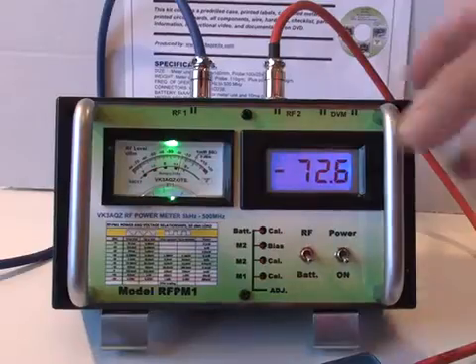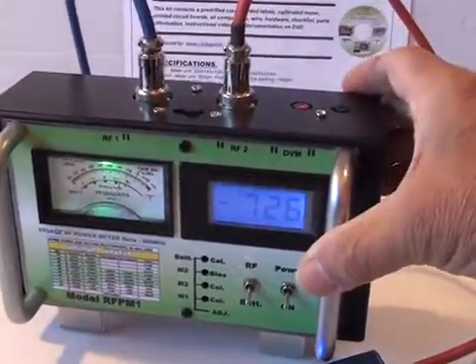The RF PM1 power meter can be calibrated by connecting a digital multimeter to a couple of 2mm banana sockets on the top of the case. In this case, the 2mm banana sockets match the normal probes on digital voltmeters.